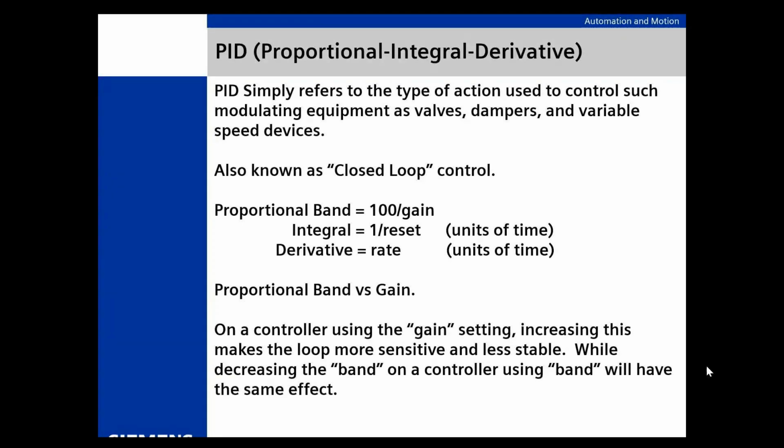Most people don't talk about gain anymore. Okay, they talk about proportional band. Gain's kind of the inverse of that. Gain is something that we used in the pneumatic days. People talked about the gain. Well, the gain of the controller needs to match the gain of this. That's kind of gone now. I don't know that anybody really talks about gain. You may hear it a little bit, but again, the guy's probably over 60.